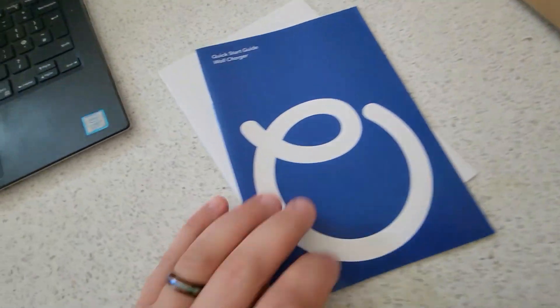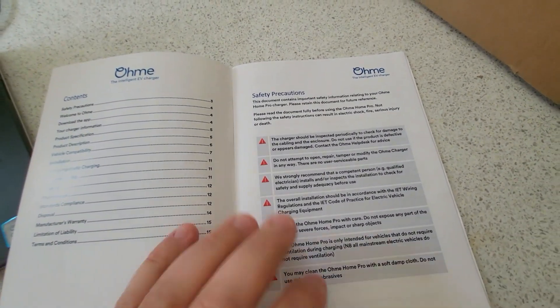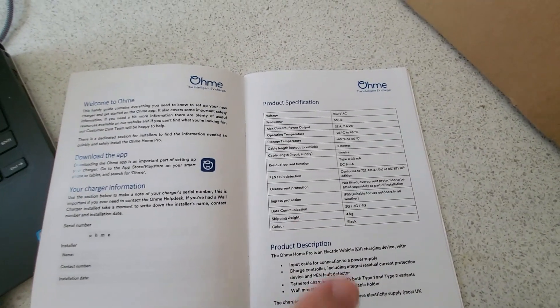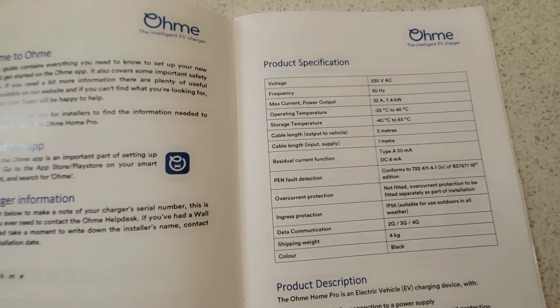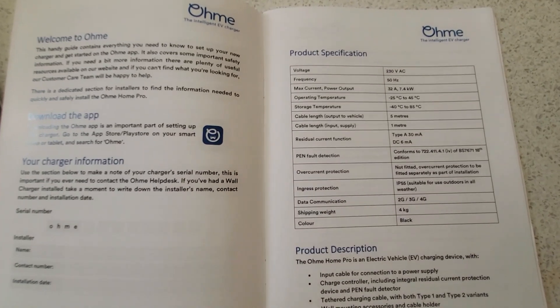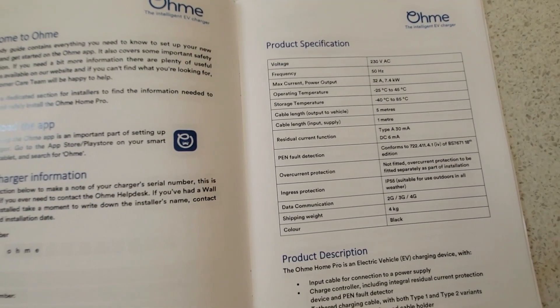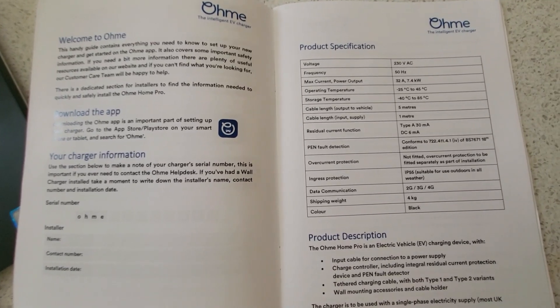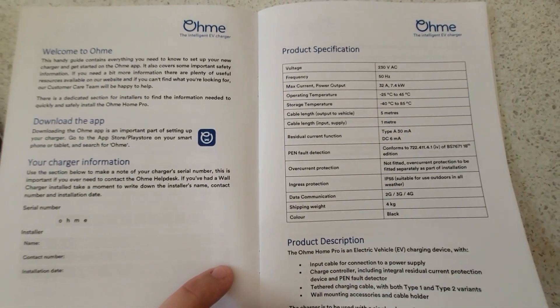The way this has to be wired is that the pre-wired lead goes into a junction box close by — a metre isn't usually going to be anywhere near long enough. Looking at the manual, it's got Type A 30mA RCD protection built in, plus DC 6mA as well, so everything in terms of RCD protection is built into the charger. It also has PEN fault detection, and they've specifically referenced the regulation it complies with. There's often debate about how effective these PEN fault devices are, but Ohme states this meets the intent of that reg.